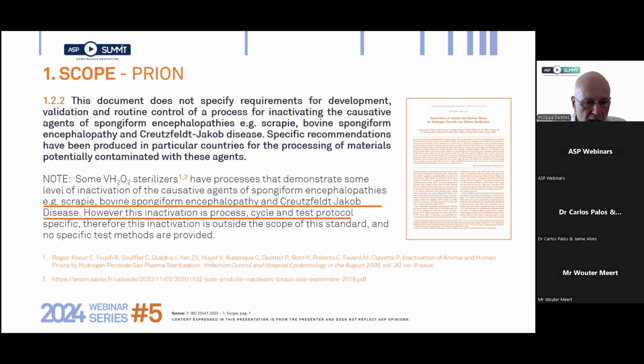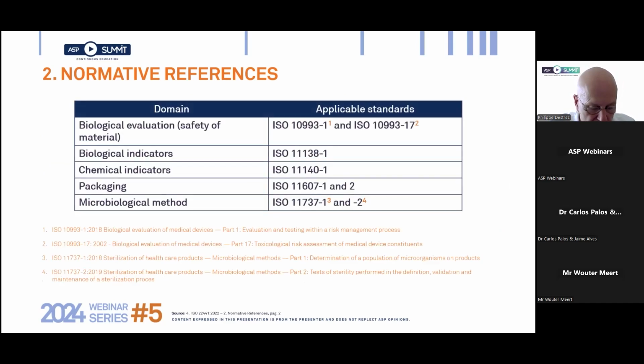And in the next slide, we'll be saying a few things about prion. The scope of all process standards, not only H2O2, but also steam and other standards, excludes prion inactivation. In the case of H2O2, this is not because H2O2 does not work on prion, but there is currently no ISO standardized method for prion inactivation. There are, however, very well recognized scientific protocols and criteria to evaluate prion inactivation, and they showed the superior efficacy of H2O2 compared to other sterilization methods. And some cycles, as you know, are even able to obtain total inactivation of prion, according to a publication dated from 2009.